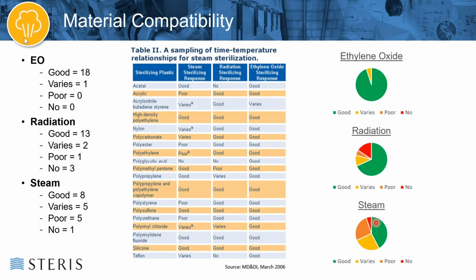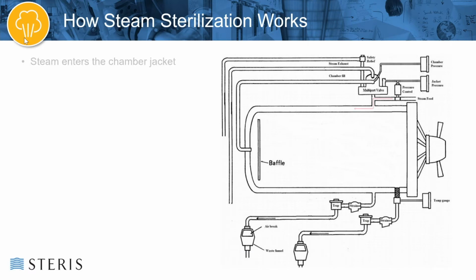So now I want to talk briefly about how steam sterilization actually works inside the chamber. This is a real high-level graphic representation of a steam sterilizer. What happens is that steam enters the chamber jacket from the steam feed. The jacket is the space that surrounds the actual chamber. So steam will come into this space from the steam feed, and then the jacket pressure is controlled with a feedback loop. We have a pressure control and jacket pressure gauge. There's a feedback loop that monitors the jacket pressure and keeps it at the appropriate set point.